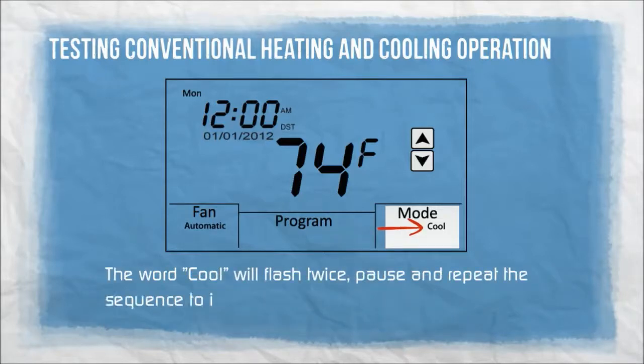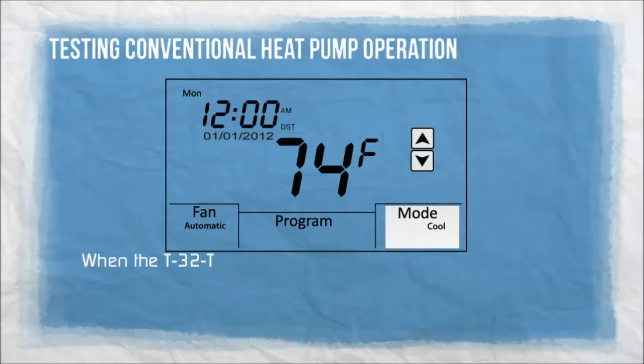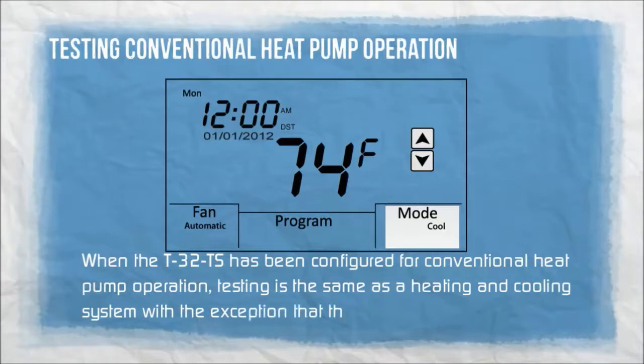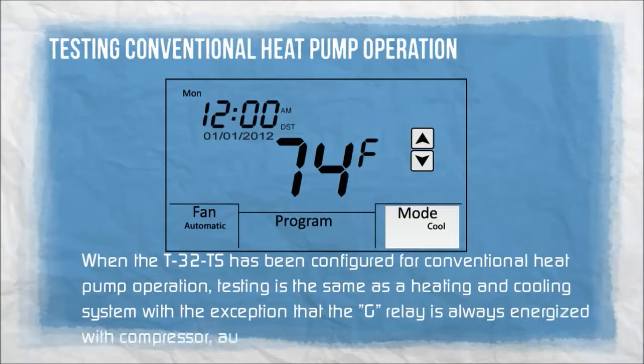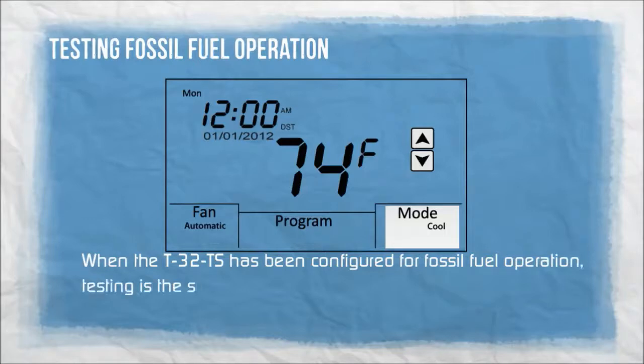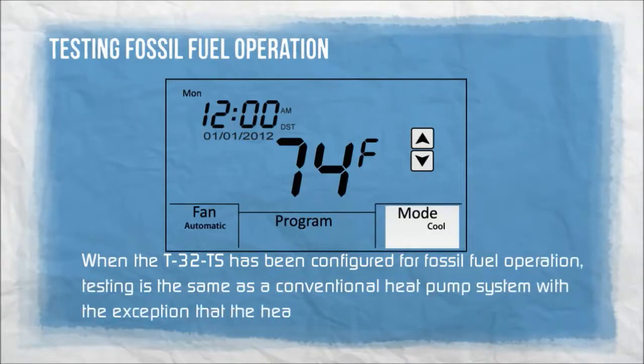When the T32TS has been configured for conventional heat pump operation, testing is the same as a heating and cooling system with the exception that the G relay is always energized with compressor, auxiliary, and emergency heat calls. When configured for fossil fuel operation, testing is the same as a conventional heat pump system with the exception that the heat pump is never allowed to run when the fossil fuel furnace is energized.